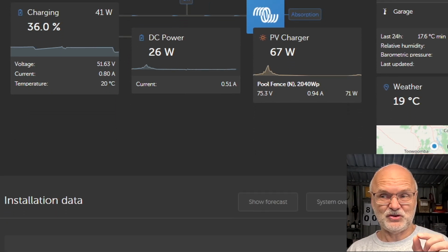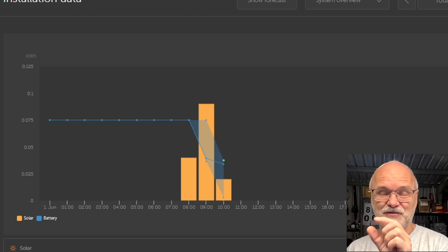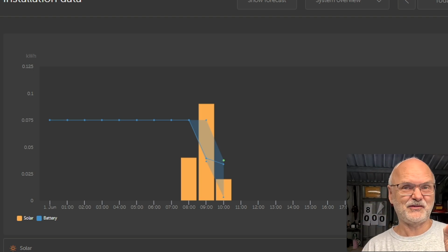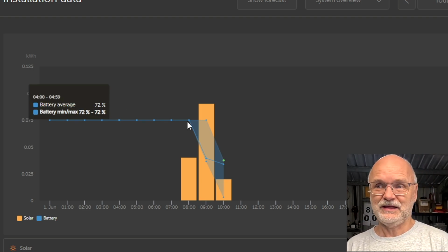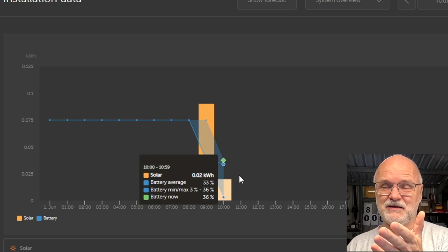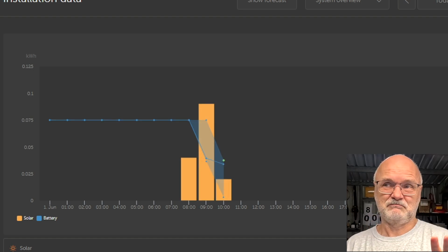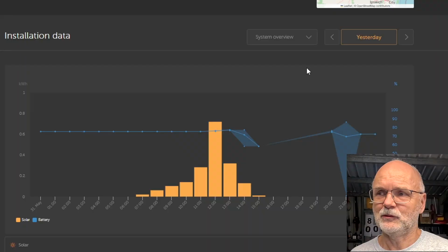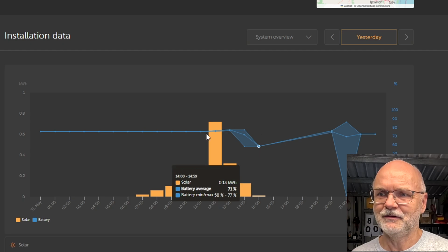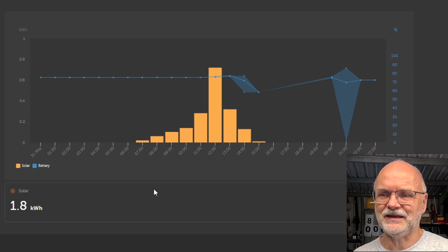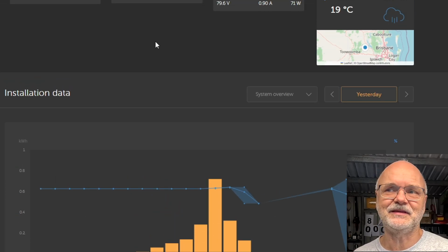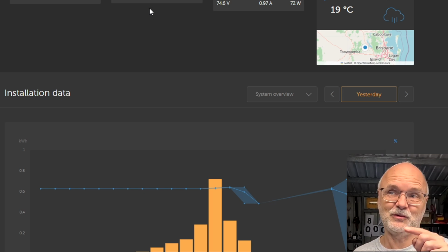From now on, we should actually see a red bar coming up because the system now knows there is a load connected, which is a DC load, and it should give us a red bar showing the consumption, but it doesn't. If we look at yesterday, this was before I connected the tower of power. You can see we charged 1.8 kilowatt hours into the system and I had DC power turned on. I've just turned it off this morning to see if it makes any difference. It doesn't. Whether DC power is turned on or not makes no difference at all.